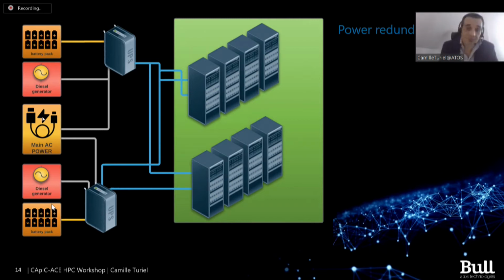So generally, it's advised to have a dual power source at the beginning of your data center, or your own transformer. On top of that, the very common setup is to have, on top of this dual UPS, a diesel generator, generally also redundant, or at least one power generator.